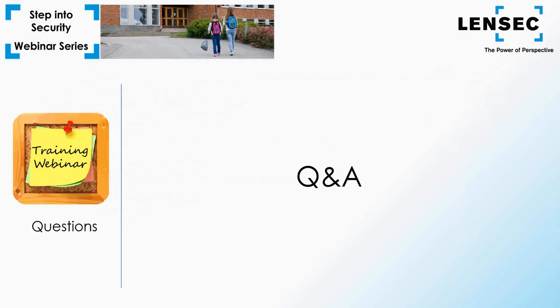Good job Keith. A few questions came in — let's squeeze one or two in. First question: which version of the building and fire codes should I follow? The right thing to do is to follow the version of the code that the AHJ follows — that could vary among entities. The most recent version of NFPA 101 is 2015, but many jurisdictions are still working off 2012 rules or earlier, or even a different ruleset altogether. The AHJ has the authority to adopt the code, so check with them for clarification on which code they follow.